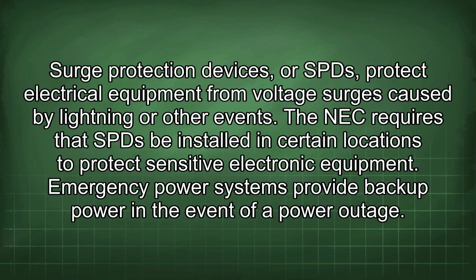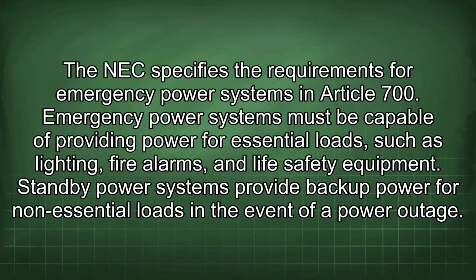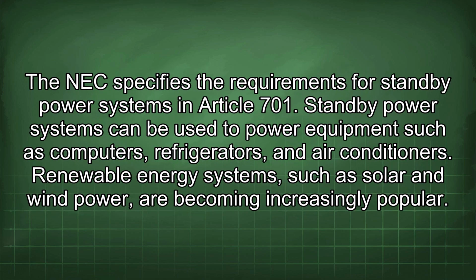Emergency power systems provide backup power in the event of a power outage. The NEC specifies the requirements for emergency power systems in Article 700. Emergency power systems must be capable of providing power for essential loads such as lighting, fire alarms, and life safety equipment. Standby power systems provide backup power for non-essential loads in the event of a power outage. The NEC specifies the requirements for standby power systems in Article 701. Standby power systems can be used to power equipment such as computers, refrigerators, and air conditioners.